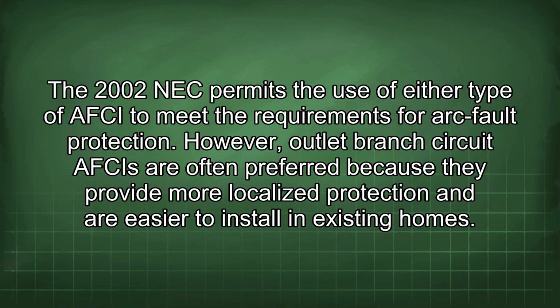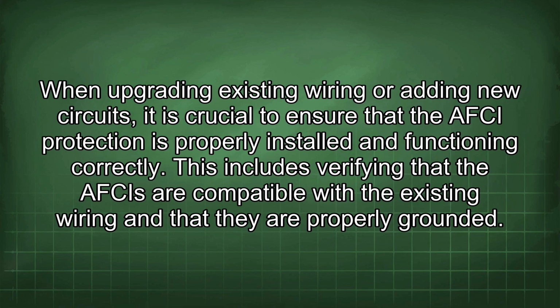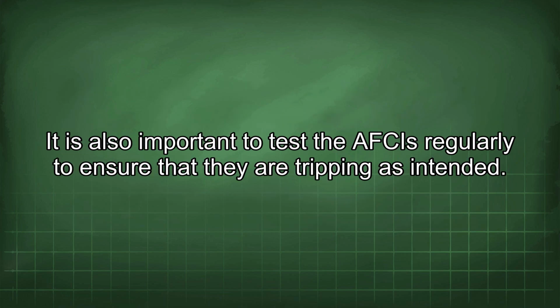in existing homes. When upgrading existing wiring or adding new circuits, it is crucial to ensure that the AFCI protection is properly installed and functioning correctly. This includes verifying that the AFCIs are compatible with the existing wiring and that they are properly grounded. It is also important to test the AFCIs regularly to ensure that they are tripping as intended.